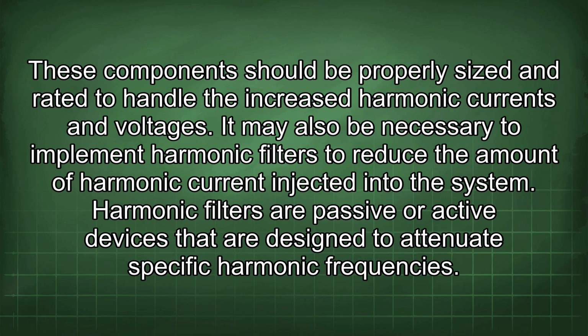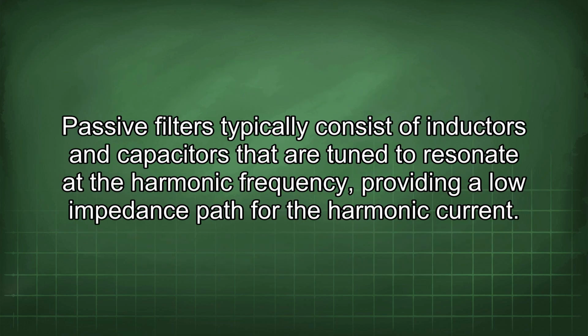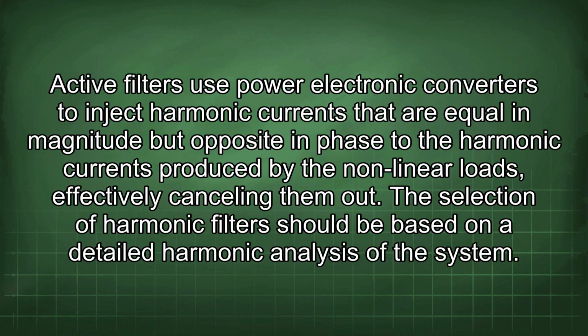Harmonic filters are passive or active devices that are designed to attenuate specific harmonic frequencies. Passive filters typically consist of inductors and capacitors that are tuned to resonate at the harmonic frequency, providing a low impedance path for the harmonic current. Active filters use power electronic converters to inject harmonic currents that are equal in magnitude but opposite in phase to the harmonic currents produced by the nonlinear loads, effectively cancelling them out.